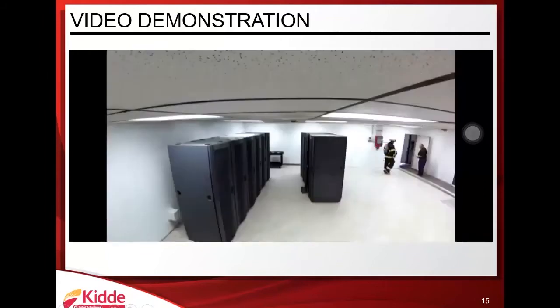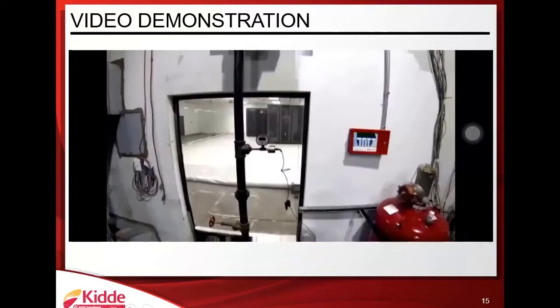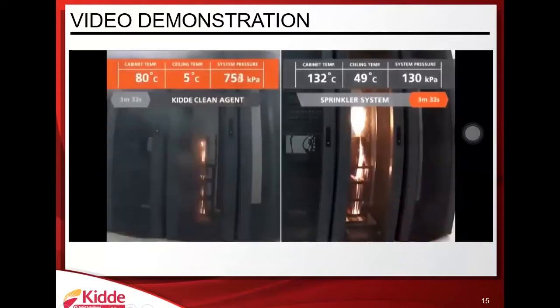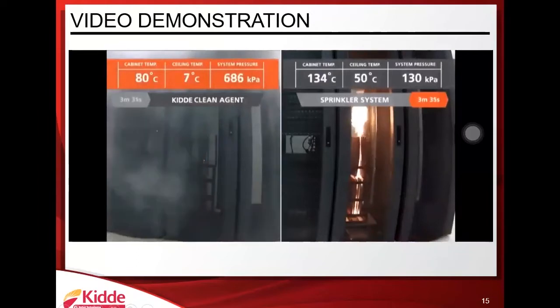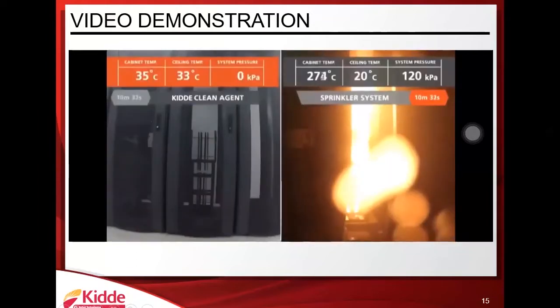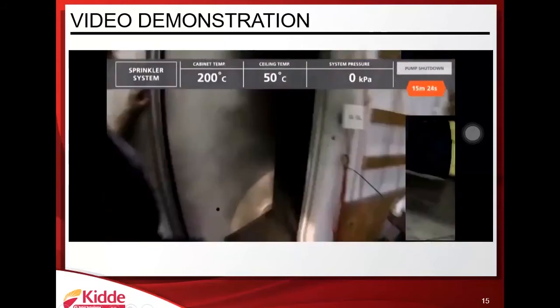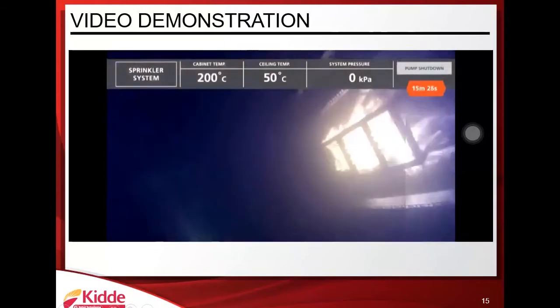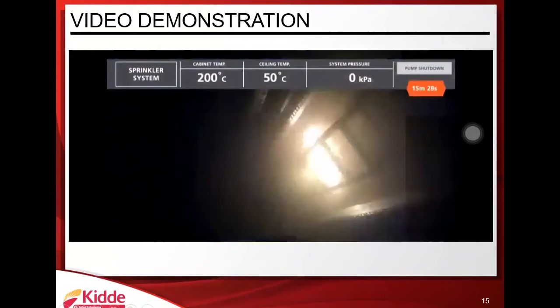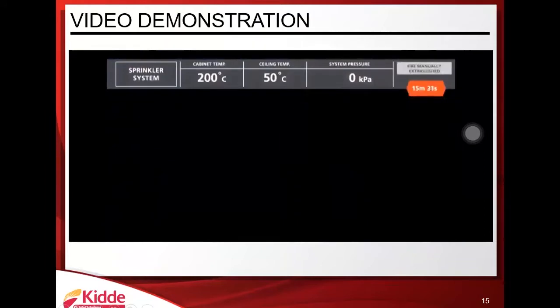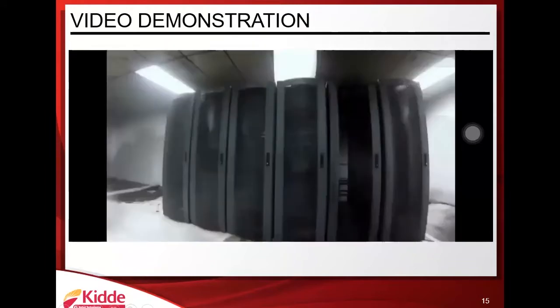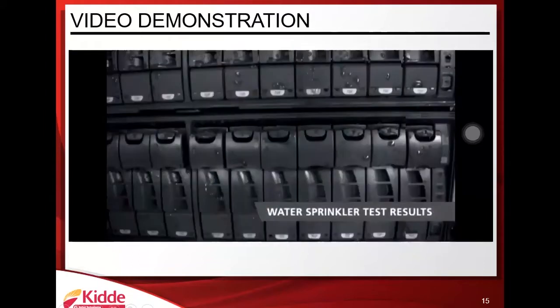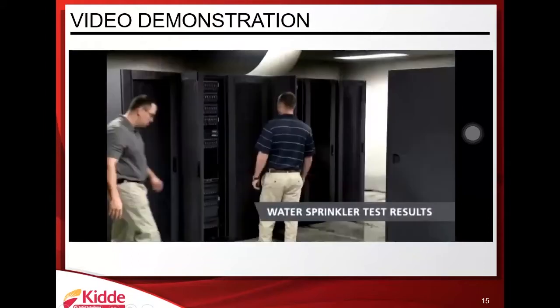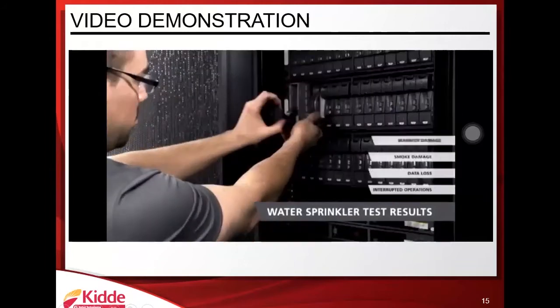The water sprinkler test begins the same way, but nearly four minutes elapse before the first sprinkler head discharges. Seven minutes later, the fire is still burning. Fifteen minutes after ignition, a firefighter enters the test chamber and puts out the fire with a portable CO2 fire extinguisher. The sprinklers did their job preventing the fire from involving the entire room, but the server equipment, walls, and ceiling are all water damaged.